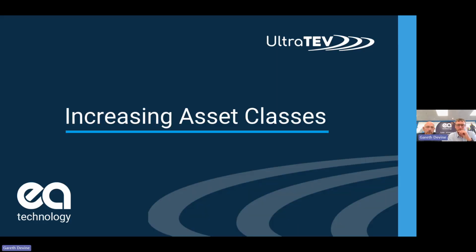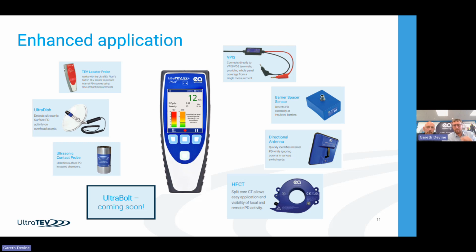So what are we doing then? The first thing we're doing is trying to increase the coverage of these devices. Over the last 12, 18 months, if you take our core handheld device, so for those who don't know, the UltraTEV Plus 2, pictured front and centre, is our handheld device, and it's a PD platform. Built into the device are two measurement sensors: ultrasonic and TEV, looking for internal discharge, originally in metal-clad switchgear.